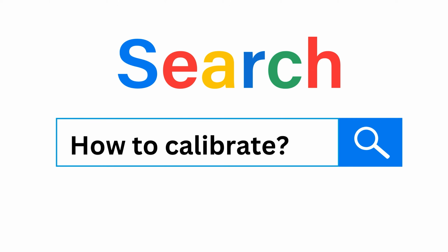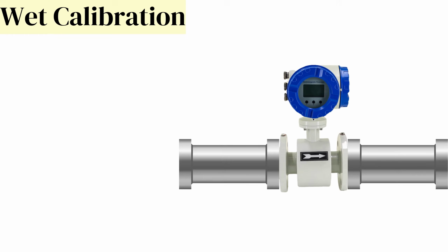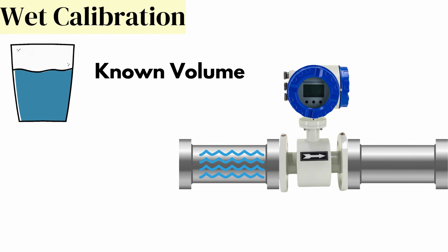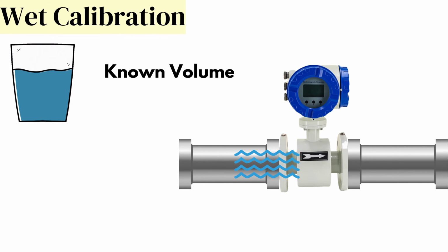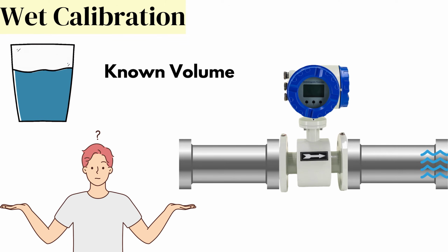Wet calibration. Wet calibration is the most accurate method for calibrating these flow meters. It involves passing a known volume of fluid through the flow meter and comparing it to the meter's reading. This process is typically performed in a calibration lab or on-site with the use of a portable calibration setup.